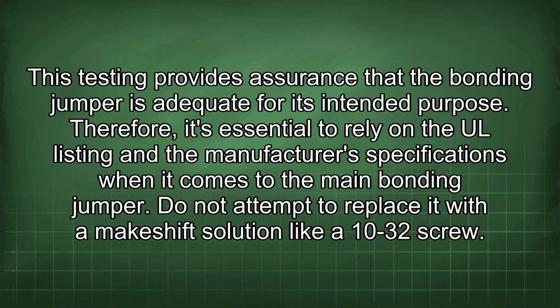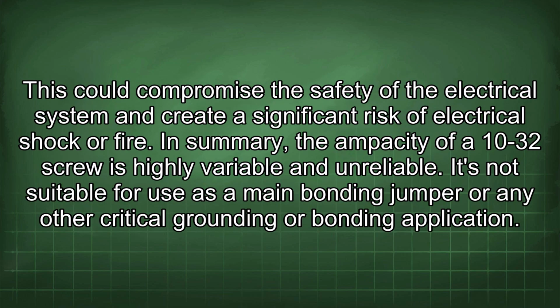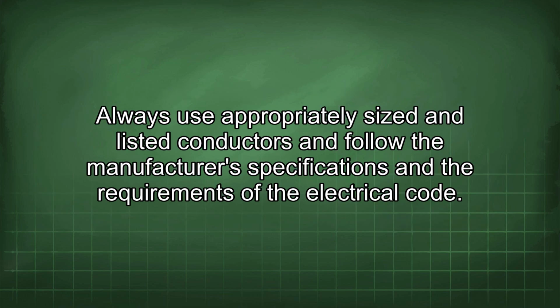Therefore, it's essential to rely on the UL listing and the manufacturer's specifications when it comes to the main bonding jumper. Do not attempt to replace it with a makeshift solution like a 10-32 screw. This could compromise the safety of the electrical system and create a significant risk of electrical shock or fire. In summary, the ampacity of a 10-32 screw is highly variable and unreliable. It's not suitable for use as a main bonding jumper or any other critical grounding or bonding application. Always use appropriately sized and listed conductors and follow the manufacturer's specifications and the requirements of the electrical code.